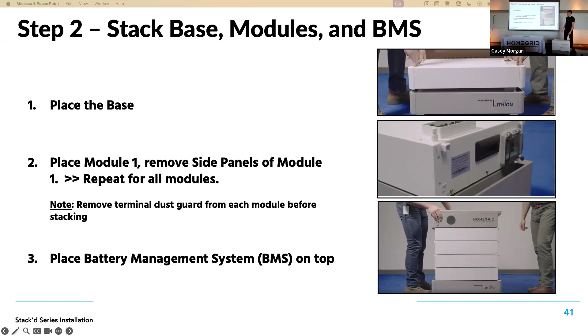You can see here there are dip switches 1 through 6. You're going to number those according to the module's position in the stack. This is in our manual, but for reference you can take a picture of it. It's binary: the top module has the first dip switch up, and so on down until 8. If you just had 4 modules, it'd be 1 through 4. That basically tells the BMS where the module is in the height, or in the stack.